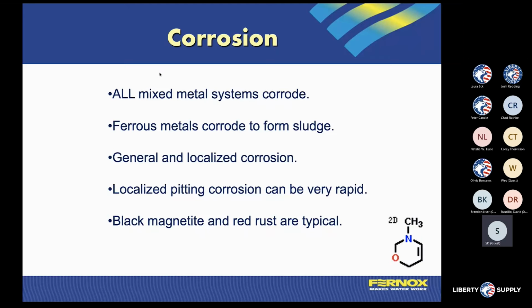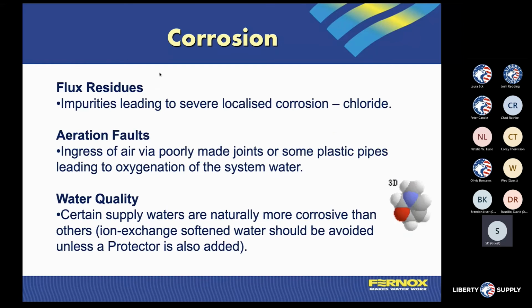Not that any one of them is bad, but we need to deal with the fact that that material is going to end up in our fluid for our heating and cooling systems. Because of that, it affects our water quality. So even if we had perfect water or perfect fluid, no matter if it's a glycol-based solution or a straight water-based solution, we're going to inevitably have a change in our fluid from that standpoint.